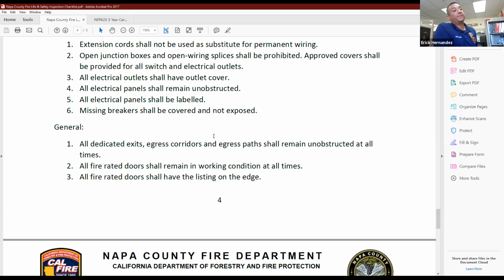So, two things. There is a code section in the California Fire Code that states that you shall provide a minimum of 3 feet of clearance around the actual electrical panel. But if it's inside a room where it's not the main panel, there is another code section that states that there shall be no combustible storage in any electrical, mechanical, fire pump, or riser room. So let's stay away from that. Let's make sure that we have adequate access to these utilities.